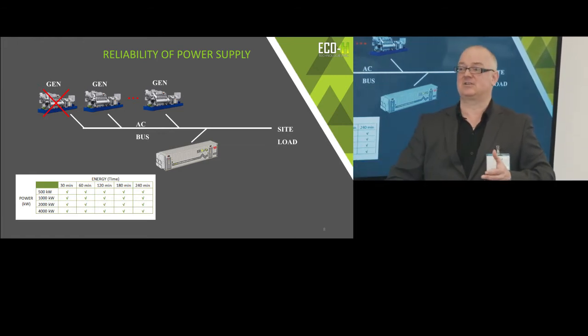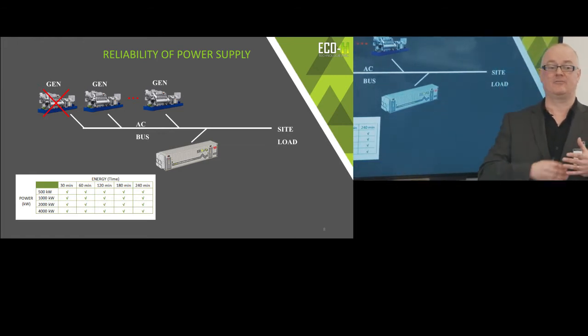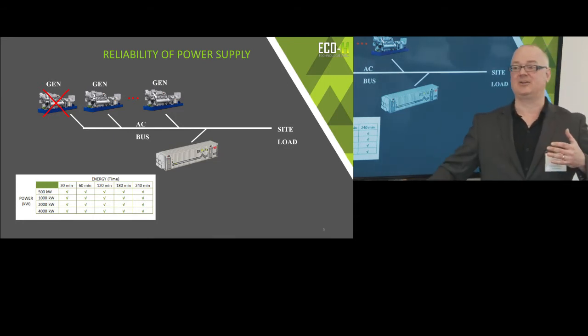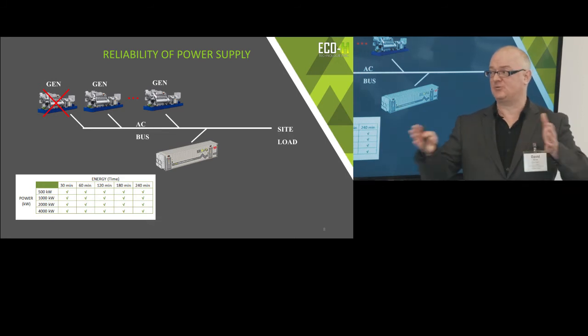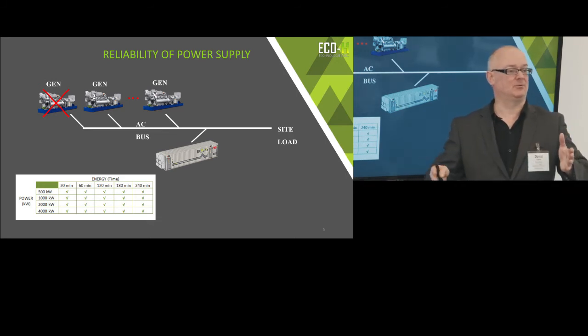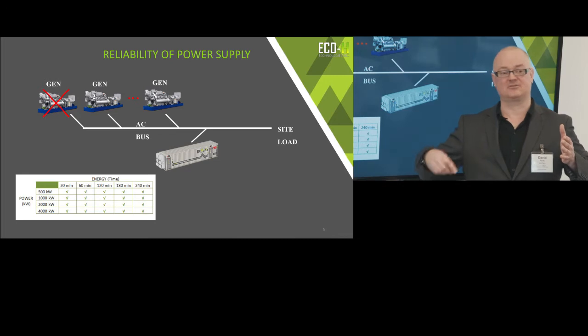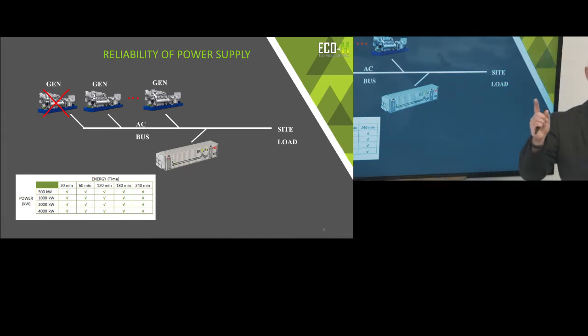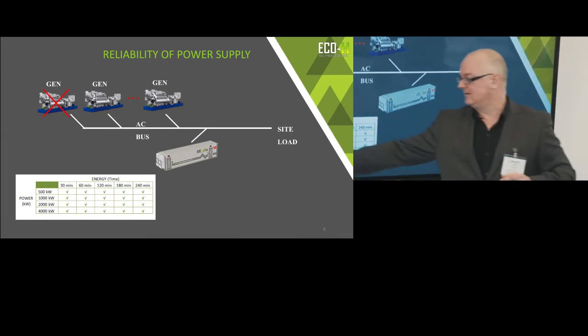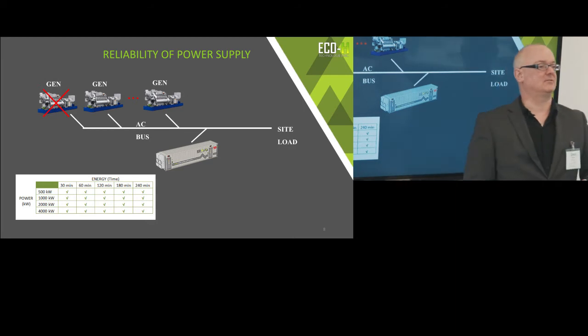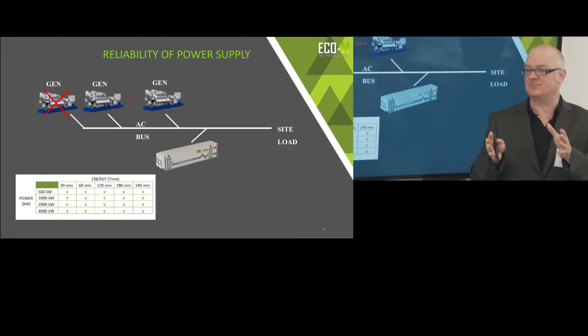Conversely, if you want to take over transients, or for blackout protection - if you're on utility and you lose utility, the generators backing up take about a 15, 20, or 30 second delay before they're up to speed. In that delay period, you might need 4 megawatts for 25 seconds or a minute. So you need a lot of power, but very, very small energy components.